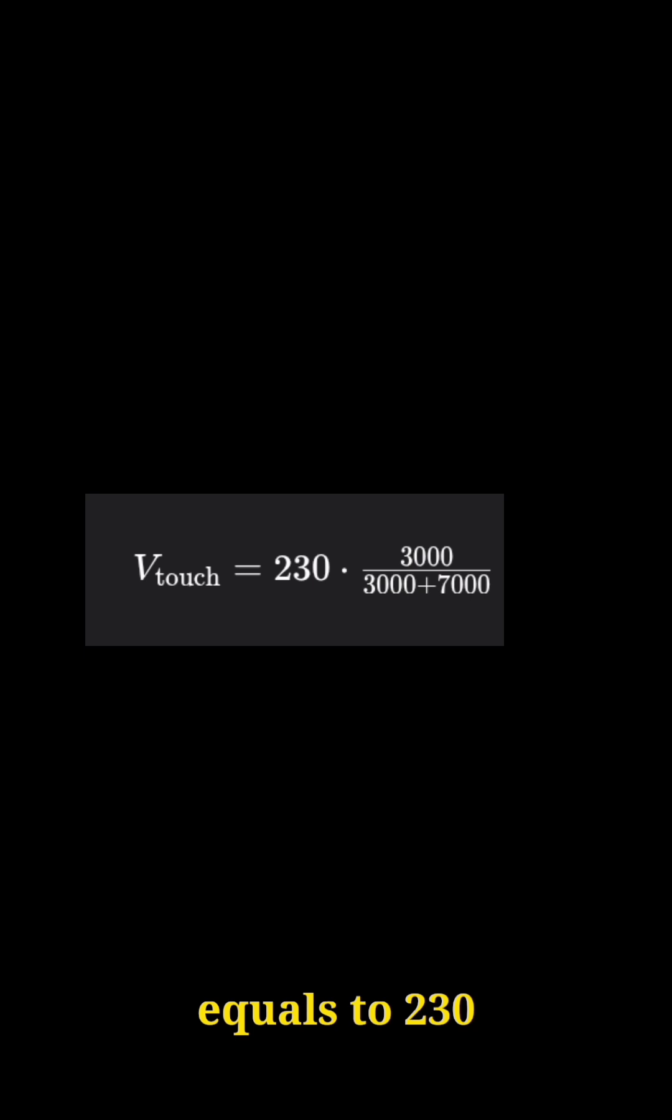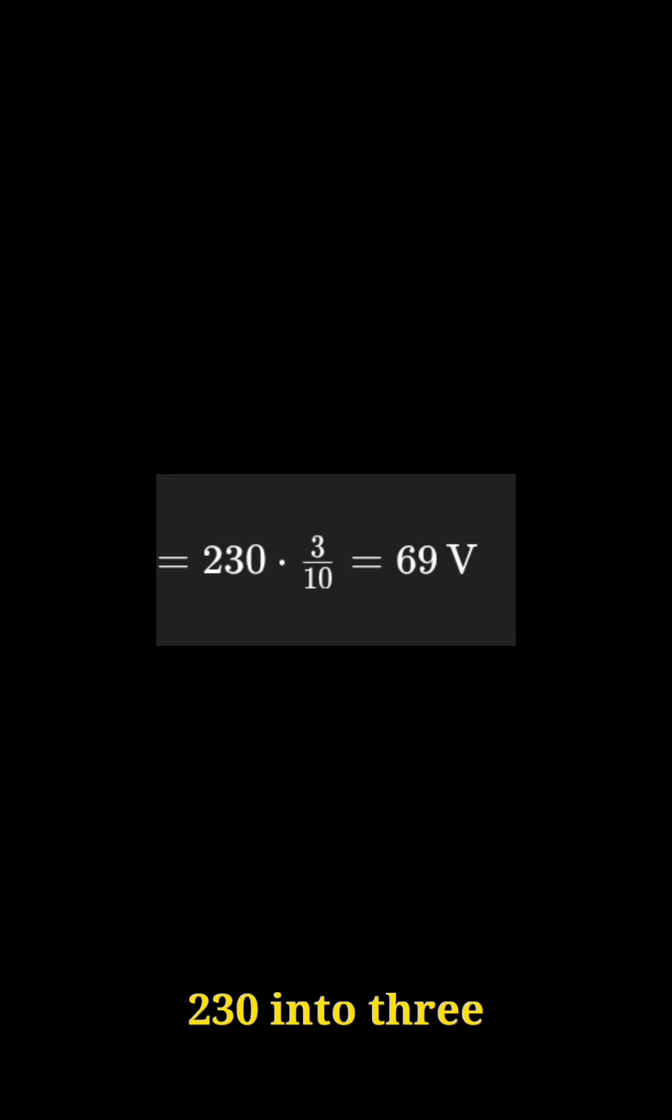Calculation: V touch equals 230 times 3000 divided by 3000 plus 7000. Using the voltage division rule, this equals 230 times 3 divided by 10, which equals 69 volts, or approximately 70 volts. This voltage lands on our body and is enough to cause pain or involuntary reaction.